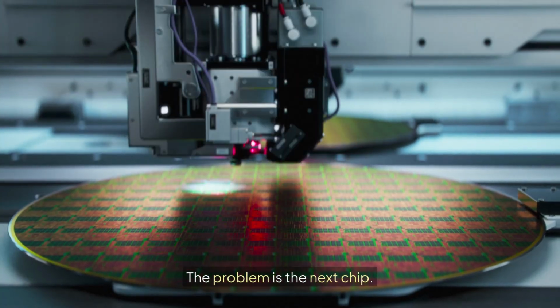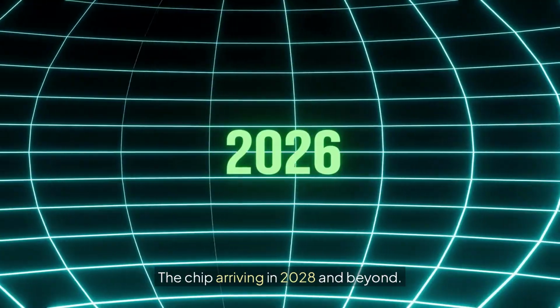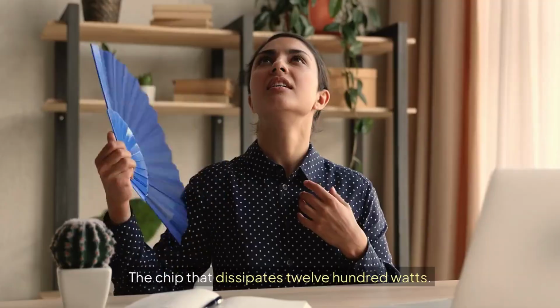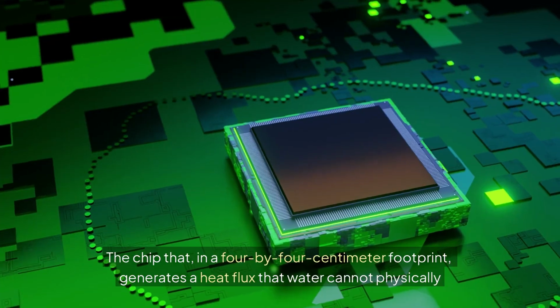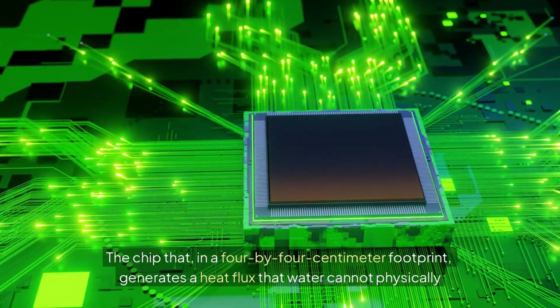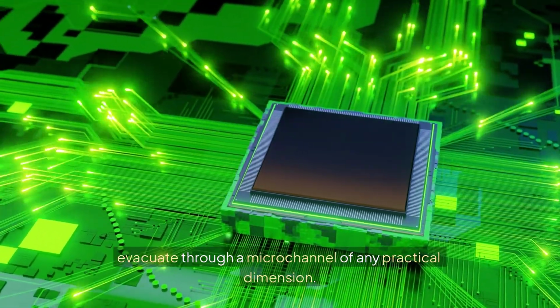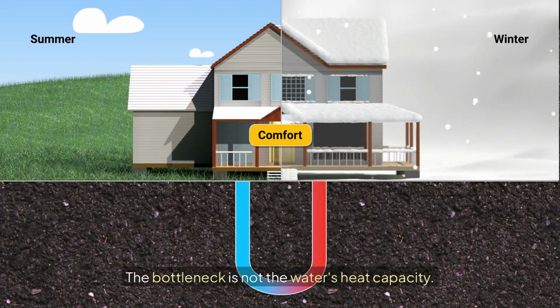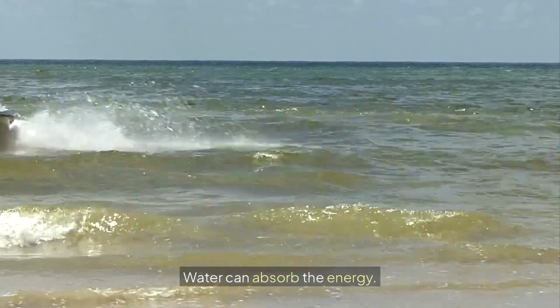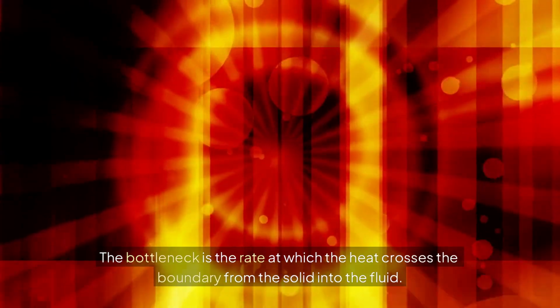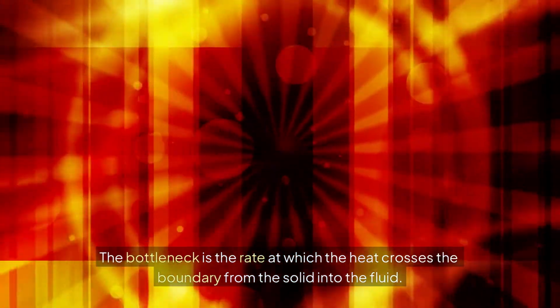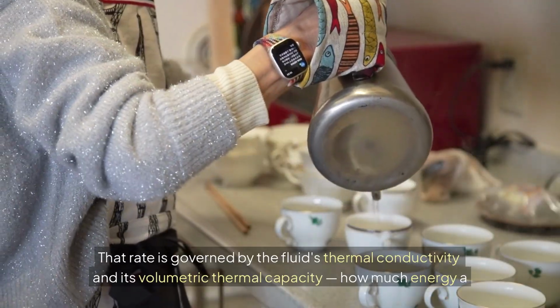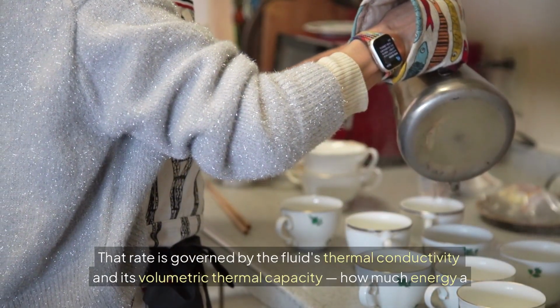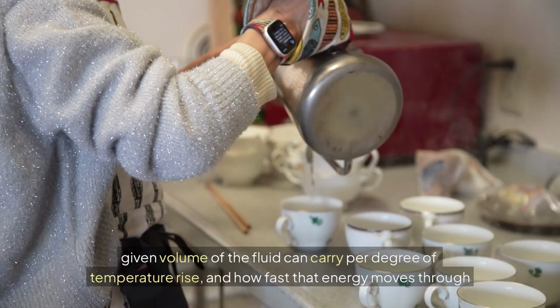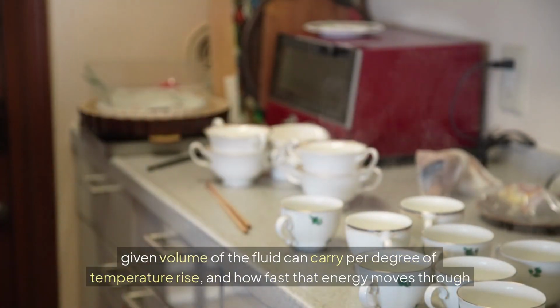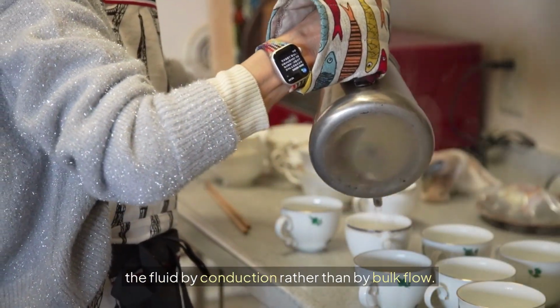The problem is the next chip, not the chip in the rack today. The chip arriving in 2028 and beyond. The chip that dissipates 1,200 watts. The chip that, in a 4x4 centimeter footprint, generates a heat flux that water cannot physically evacuate through a microchannel of any practical dimension. The bottleneck is not the water's heat capacity. Water can absorb the energy. The bottleneck is the rate at which the heat crosses the boundary from the solid into the fluid. That rate is governed by the fluid's thermal conductivity and its volumetric thermal capacity. How much energy a given volume of the fluid can carry per degree of temperature rise, and how fast that energy moves through the fluid by conduction rather than by bulk flow.